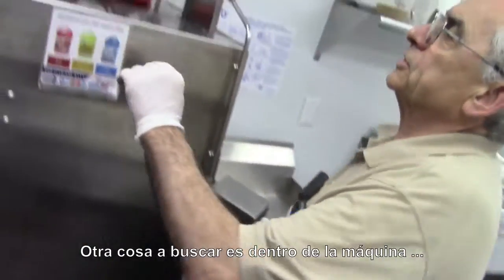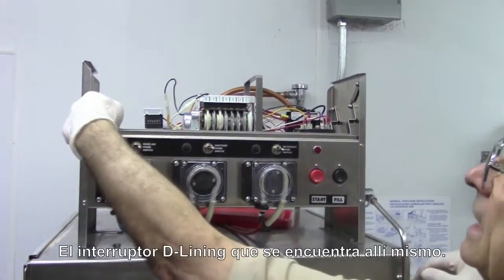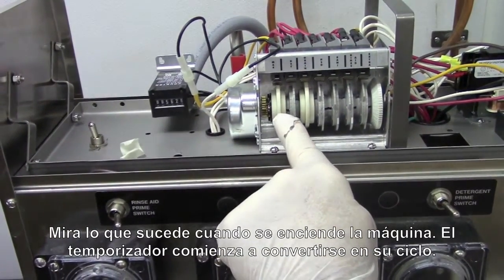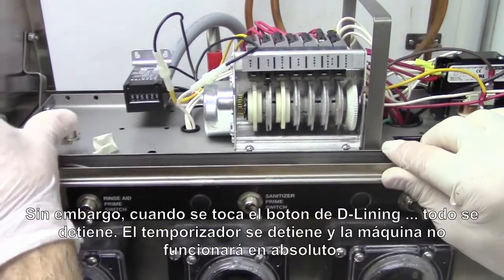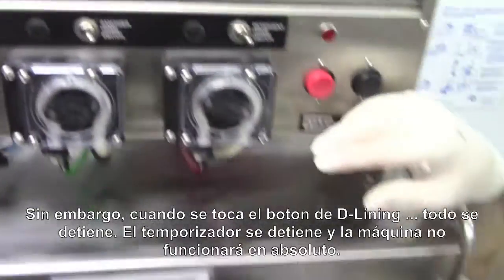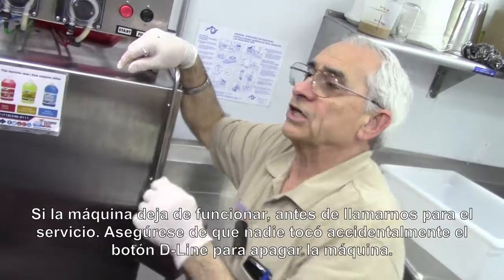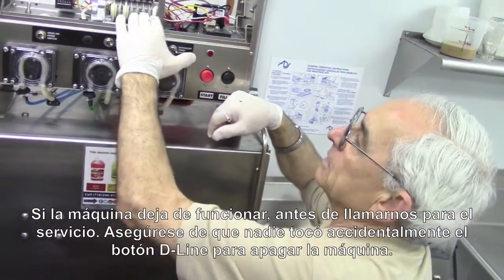Something else you should look for inside the machine — pull off the cover — is the deliming switch, located right there. Watch what happens when I turn the machine on: the timer begins to turn and work into a cycle. However, when somebody flips the deliming switch, everything stops, the timer stops, and the machine will not cycle at all. So if you go to the machine and nothing's happening, before you call for service, check to make sure that nobody has flipped this switch accidentally and shut the machine down.